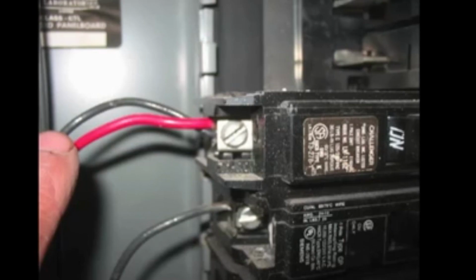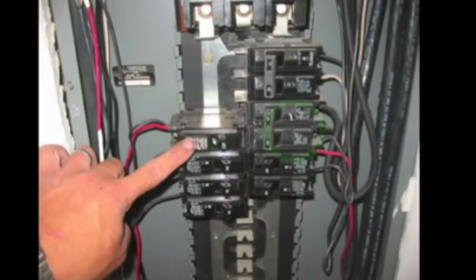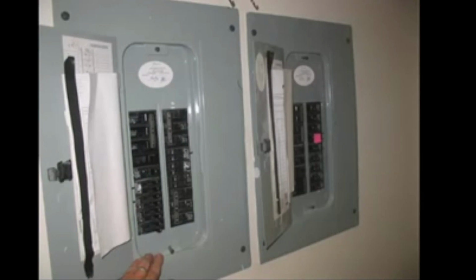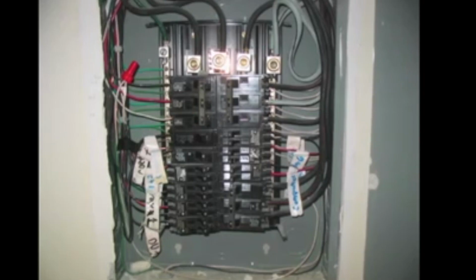Just like residential, I'm looking for obvious damage, miswiring, rust, corrosion, melting wires. This is a 14 gauge wire on a 20 amp breaker, so it's overfused. Some more panels. Take a look inside, take lots of pictures. I don't like very much the 5 grounding wires under one lug.